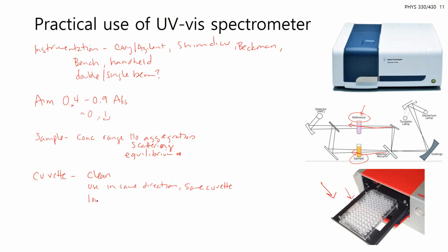And also, if you're doing a calibration curve, you always want to work from a low concentration to a high concentration, so you don't have to clean thoroughly every single time. If you're working from high to low, you're probably going to get inaccurate measurements. So these are some tips and tricks to avoid those systematic errors.